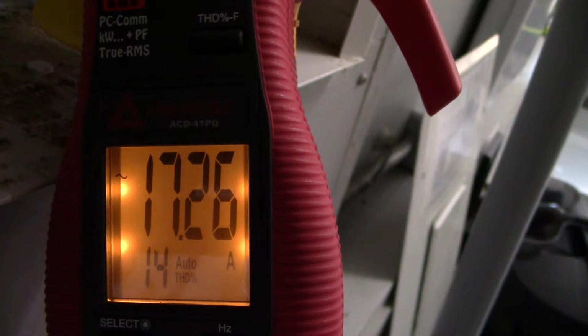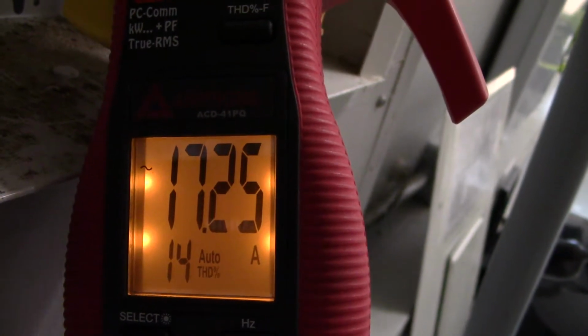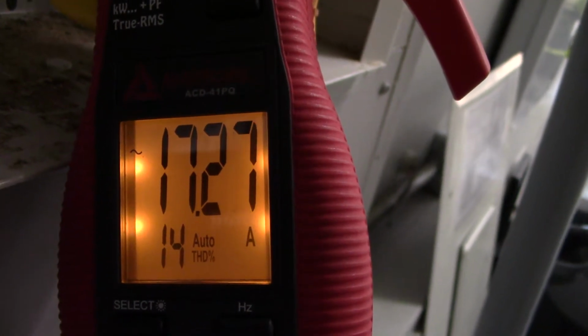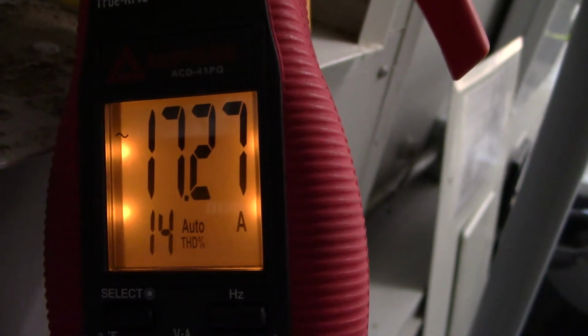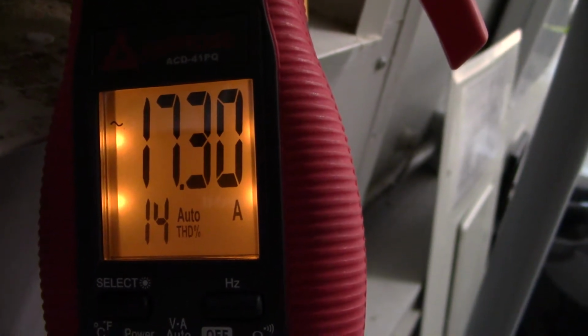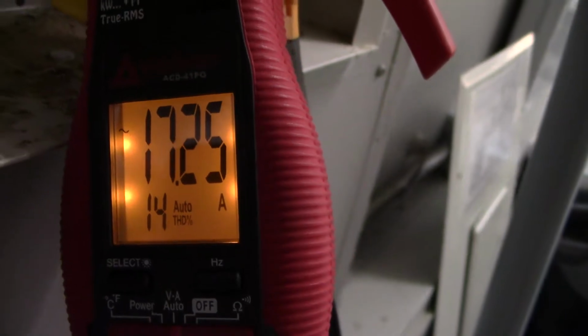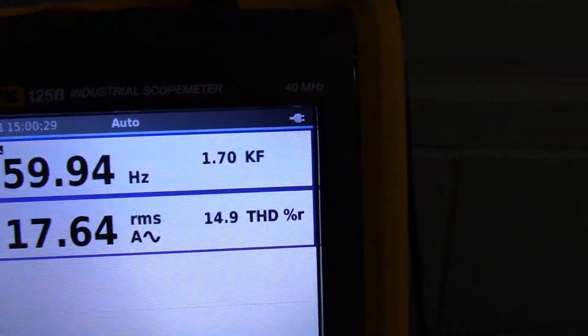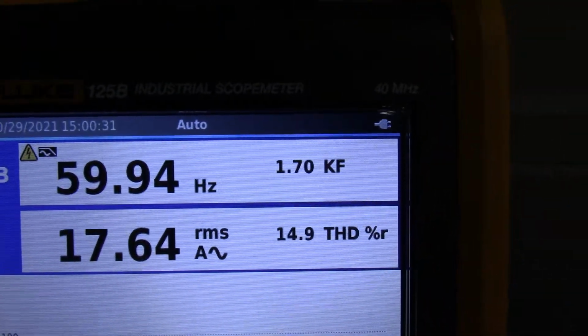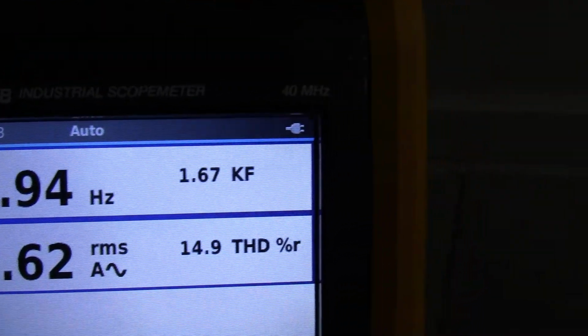So you'll notice that we have about 17.2 amps of current flow and about 14% distortion in that current. Okay, let's have a look at this meter. 17.6 amps RMS of current flow and 14.9 THD, total harmonic distortion in that signal.